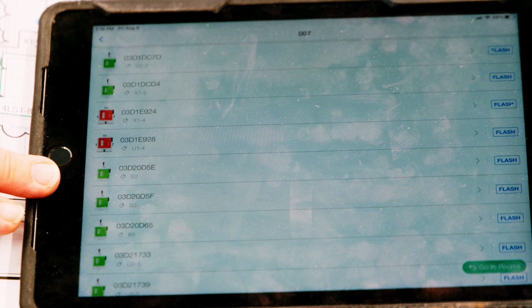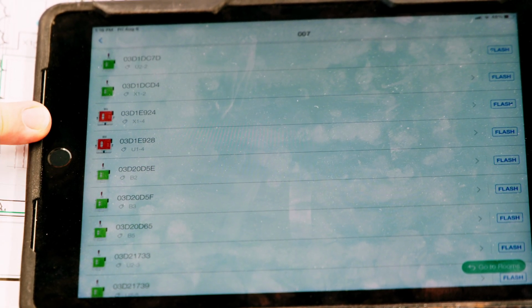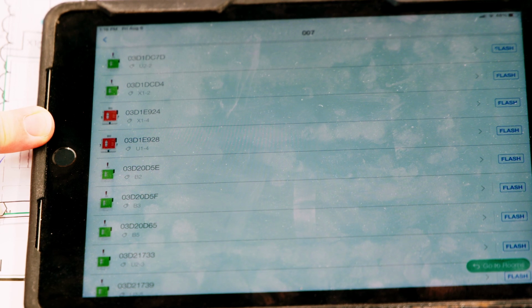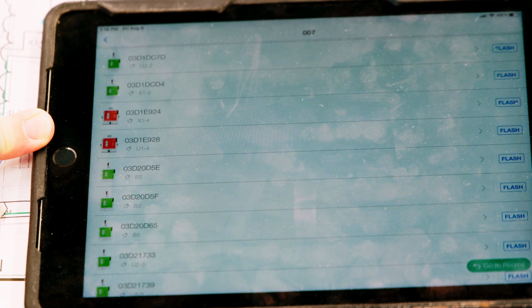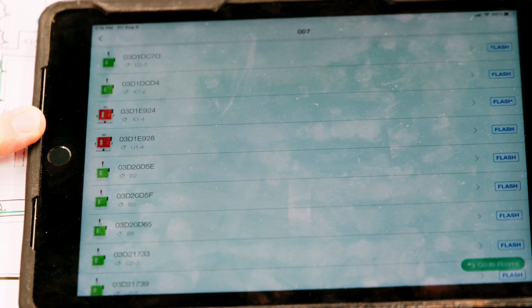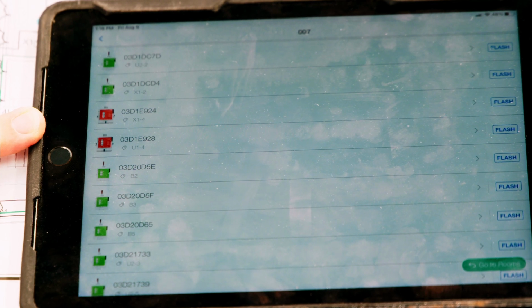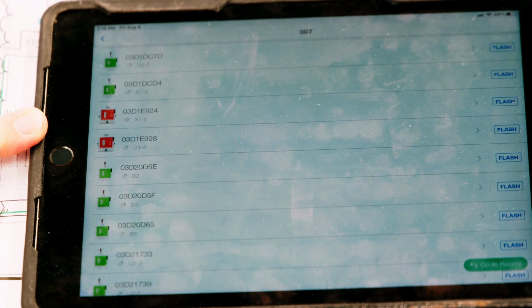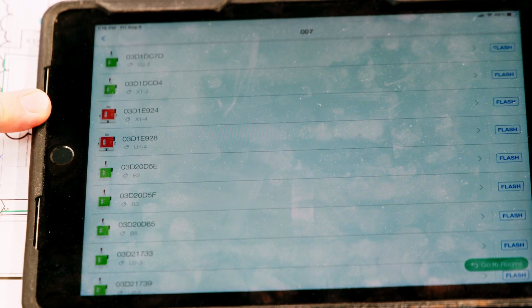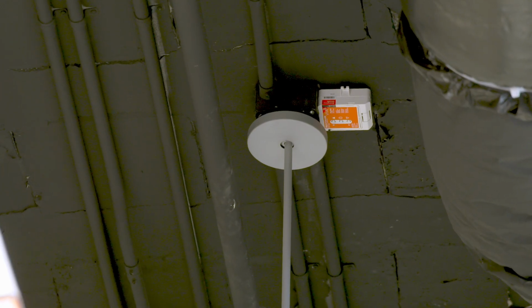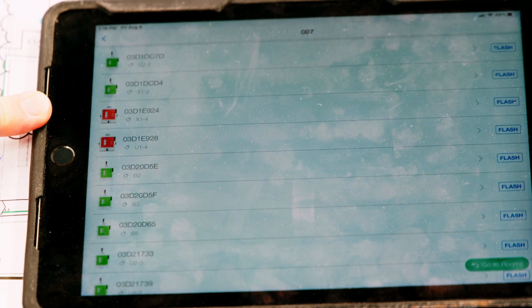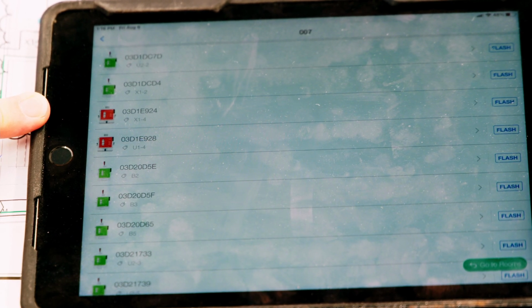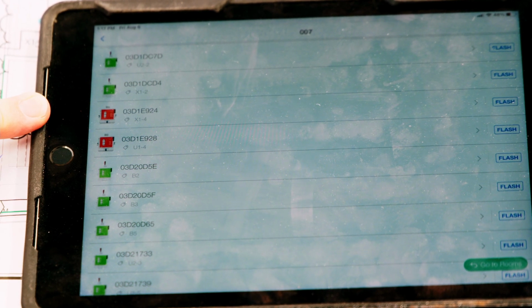The green PowPaks are normal power PowPaks. The red ones are emergency PowPaks. What the emergency PowPaks do is that when you lose normal power, the hub is on normal power as well, meaning it loses its signal. The moment an emergency PowPak loses the signal from the hub, it goes into emergency mode, meaning it turns the lights connected to it to 100%. So it takes control out of the situation.